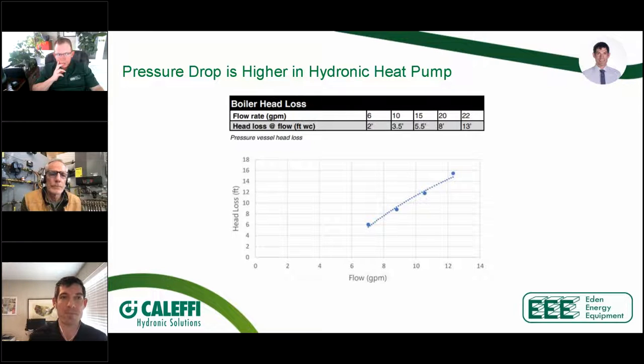So one of the things that we see, just to touch on this, and then I'll hand it over to you, Bob, is typically, again, look at that previous example where I said 5.7 gallons a minute. If it was a boiler, I'll just go back one slide if I can. I can't. This is not that case. So they would see 6 gallons a minute. They're used to boilers. Oh, it's only like 2 feet of head. Well, you've got the wrong flow rate by a factor of 100%, and you've also got the wrong head loss by a factor of 300%. Whatever you've got there is not going to work. And what's going to happen is you've got what I call a constipated heat pump. And what I mean by that is the BTUs are not leaving the BTU generator. And what happens is as the water temperature goes up, your head pressure goes up, and you end up having equipment failure. Bob?